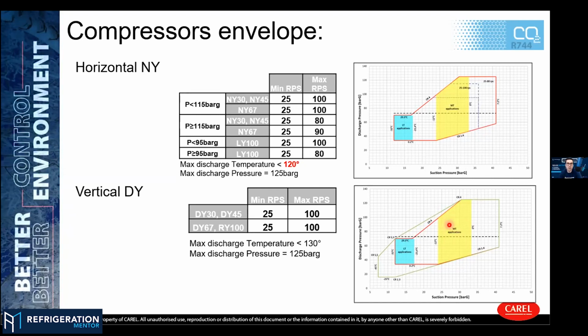Do you have software that you can plot this? They can plot the units that they're looking for, for the different applications? Yeah, we do have a selection tool where you input some values based on the cooling capacity, evaporation temperature, and condensing or gas cooler pressure, and the software will indicate the right capacity it can have for that application, heat rejection, mass flow, and so on and so forth.